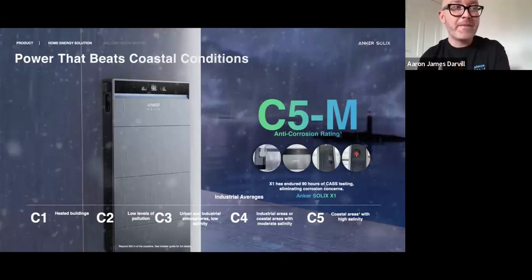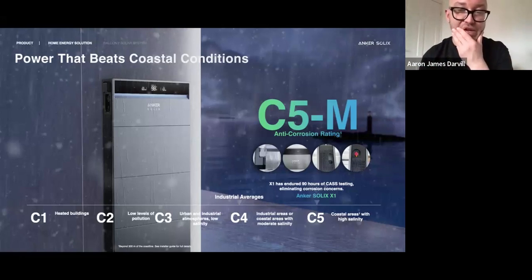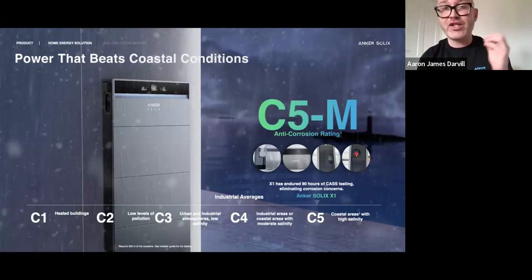So it goes back to, it's not a regulation, it's guidance about batteries being stored outside near coastal line properties. We advise that with ours, because it's had all its salinity testing, you can install this sufficiently without any casing protection as it stands 300 meters from a coastal line. You can go below 300 meters, but we would then advise you have a form of casing to protect that battery. When you look at most batteries on the market, they don't ever actually highlight their C rating.